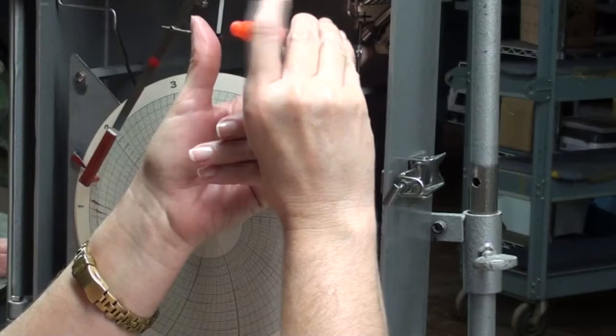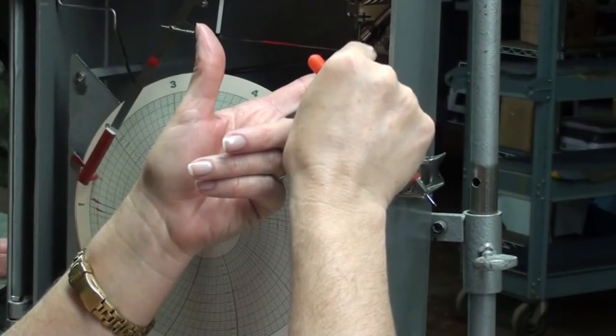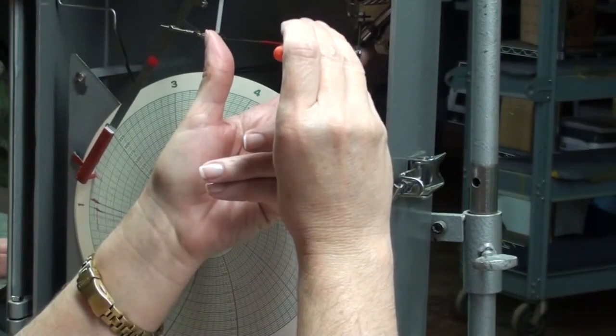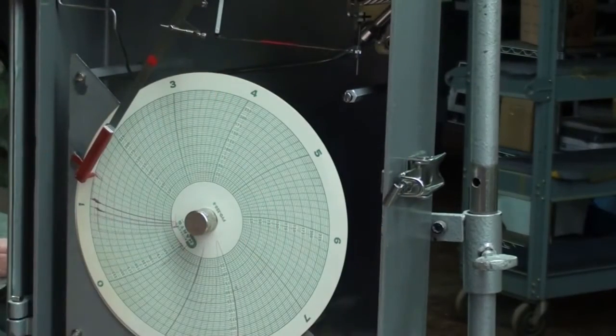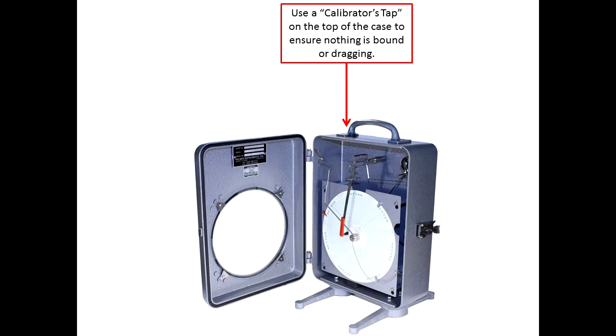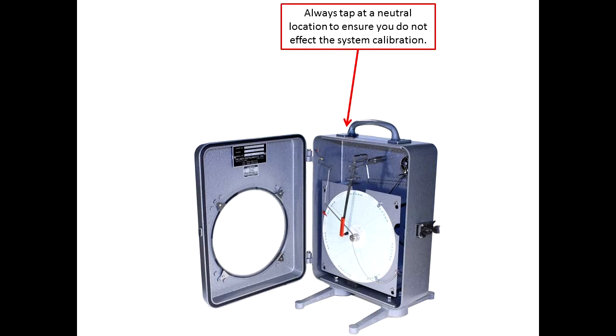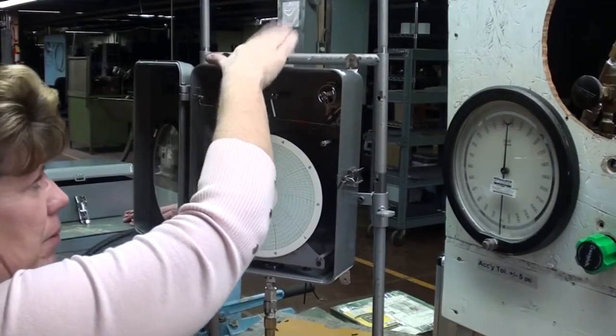I'm going to do a calibrator's tap. You always tap to a neutral location. If I were to bang my recorder real hard on this side, I could possibly cause it to read a little better one way, or if I was to do it here, I might make it look a little bit better to this side, but the correct tap is at the top of the box.